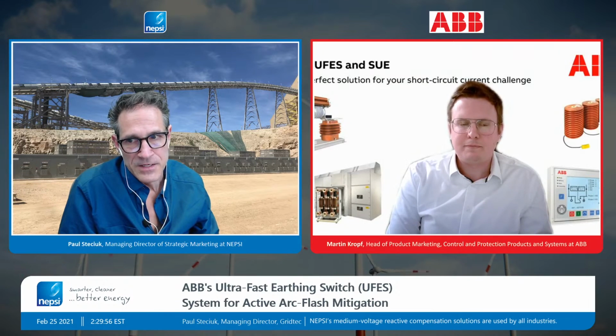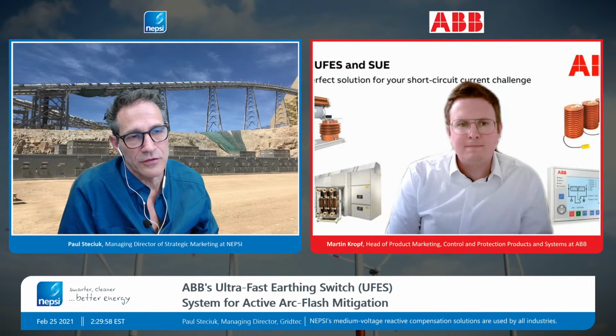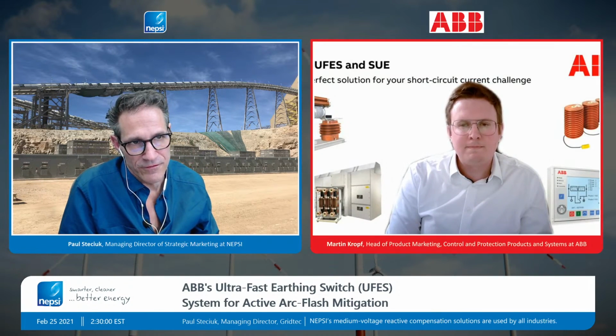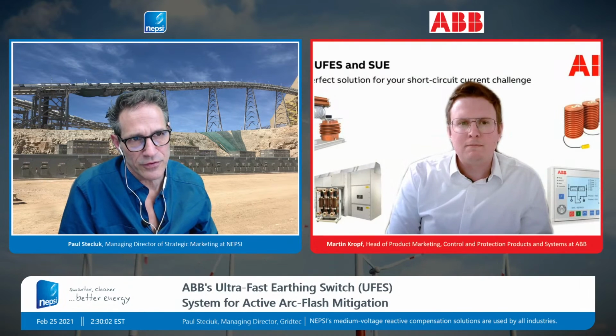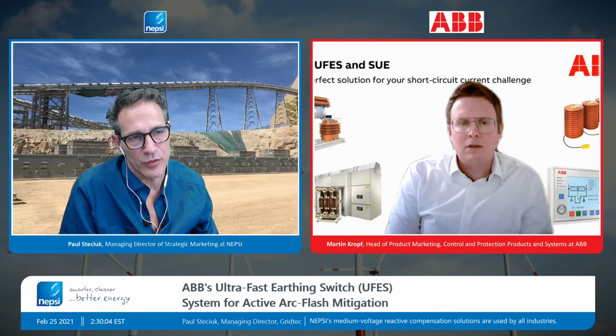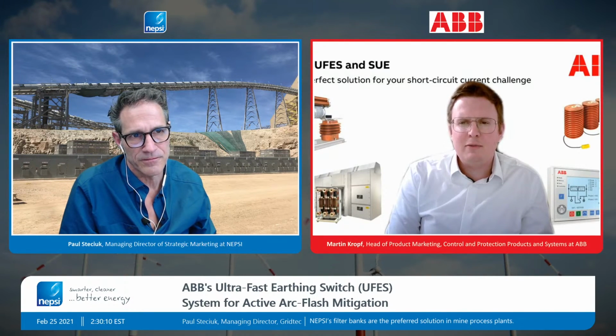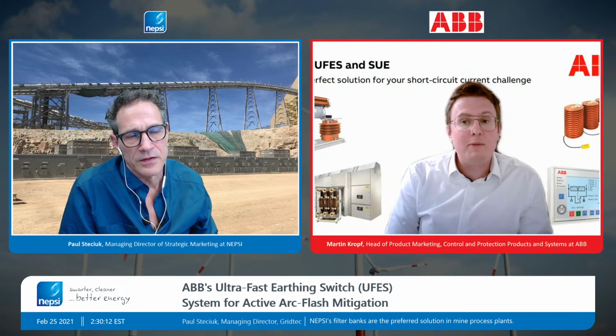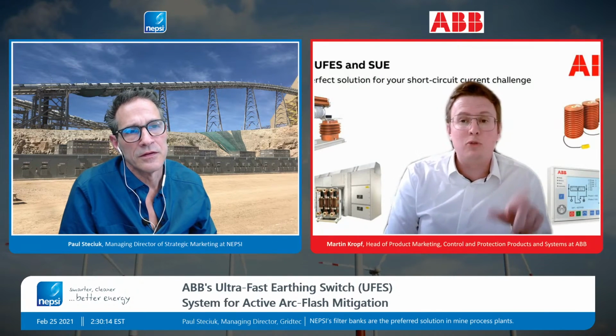I think the impulse level for this device is 150 - is that the max impulse level? 34.5 basically is what we're talking about here. I think it goes up to 150 kV BIL. The maximum we're covering, full 40.5 kV rated, means up to 200.